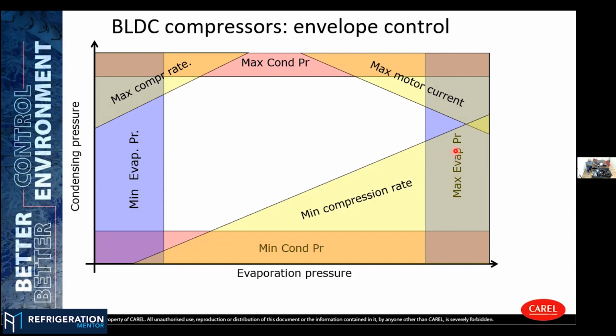The same for the maximum evaporation pressure, or as we know, MOP, maximum operating pressure. If we start to see a MOP condition, we start to accelerate the compressor and close the electronic expansion valve. We have some combined actions between compressor and valve to make this work always in the middle of the control. This is the safest zone, and the controller itself will try to make the system run all the time inside the envelope conditions. Okay, and that's super important. This is what you want to understand about inverters: they're going to try to take care of issues that are happening, but they do not fix the mechanical issue.